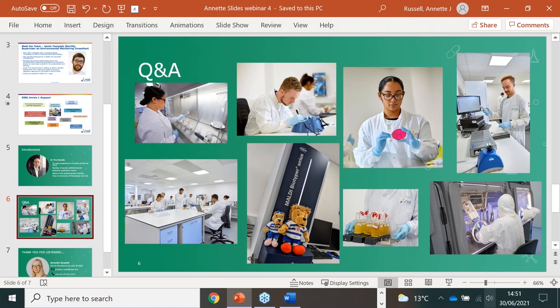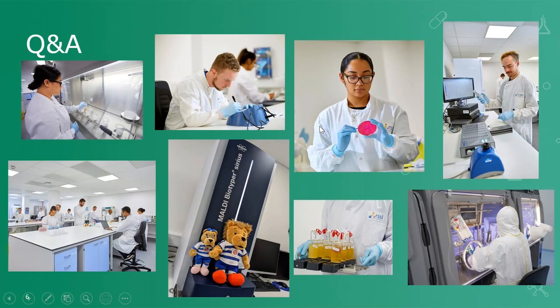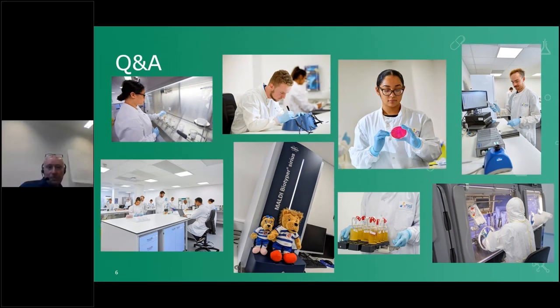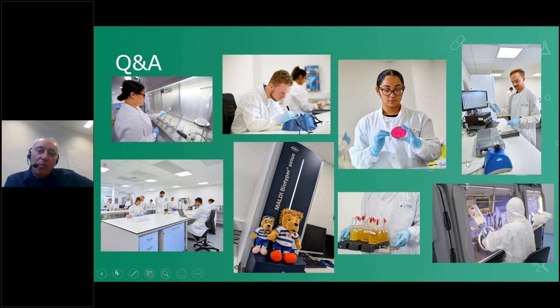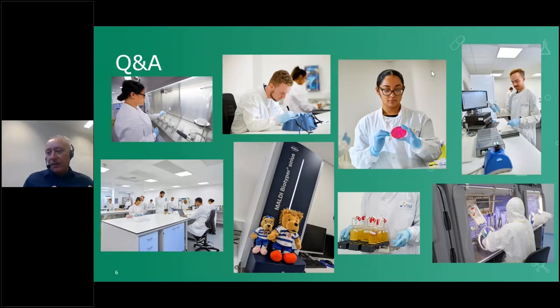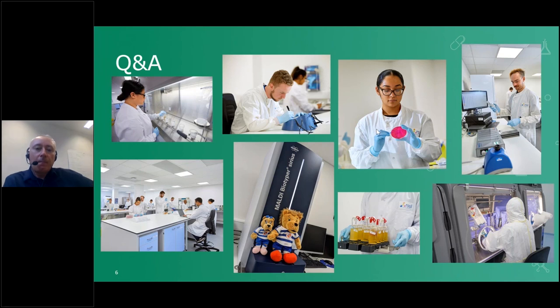We have a few questions. Kate asks: for recirculatory systems, is there a standard make-up of air in terms of percentage — for example 80/20 or 90/10? My understanding is that 80/20 is the most common, but it will vary depending on the facility design and the age of the facility. Generally, the more air you can circulate, the lower the particle challenge you're putting back into the HEPA filters, which can help prolong their life.